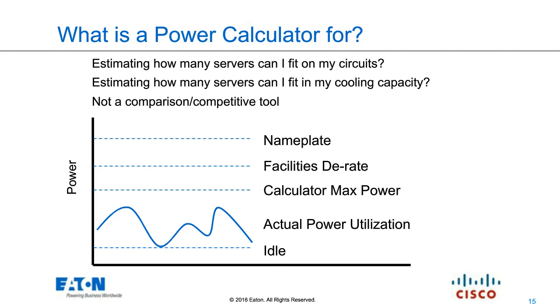But to start, the reason we do power calculators in the first place is we have these things called power supplies. If you look on the power supply, it will say this is a 750 watt power supply. Its maximum input to get 750 watts out, because it takes some power to run the power supply itself, is going to be 800 and something watts, and that will be your nameplate figure. Any facility guy or lady will tell you that input power to the power supply, you'll never even come close to it, because it's an engineering number, and engineers always over-design their power supplies. It's just what you do.